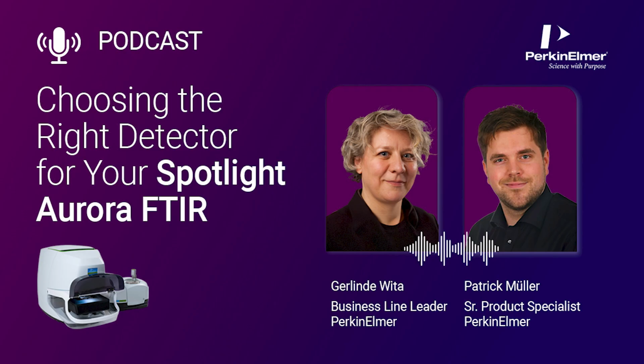Yeah, one that might come to mind from what I said up to now is that for some of the detectors, you need liquid nitrogen, which is obviously a choice you have to make beforehand regarding availability of liquid nitrogen, maybe safety concerns you would have, and convenience and ease of use. Because obviously with liquid nitrogen, you have the cool down time of your detector when you fill it with the liquid nitrogen. And both the thermoelectrically cooled MCT and the InGaAs detector do not have this problem.